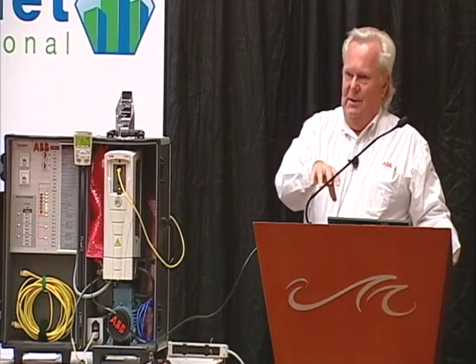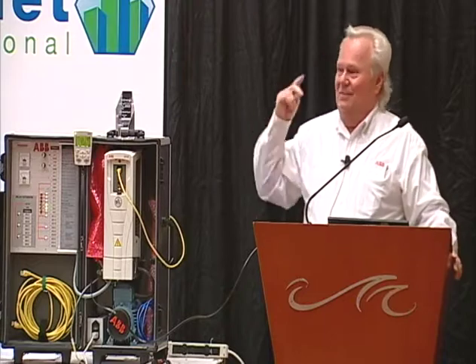So I want you wiring the damper control actuator and the damper proof back to the VFD, because what if you go to a bypass? You go full speed right now, you blow up that duct right now. Probably before the overpressure switch can catch it, if you hopefully have one, right? So safeties and damper control, I just flat say you need to wire those back to the product.